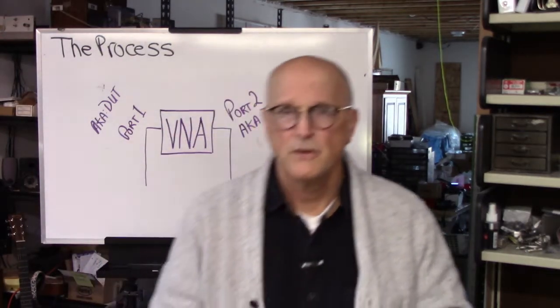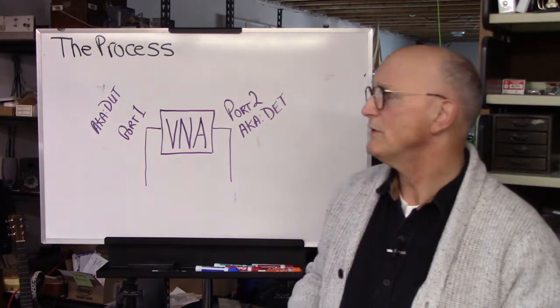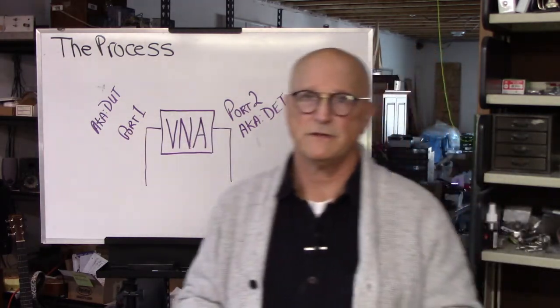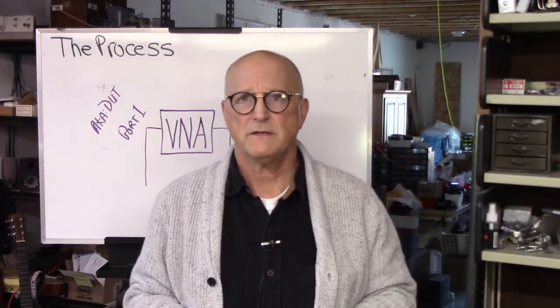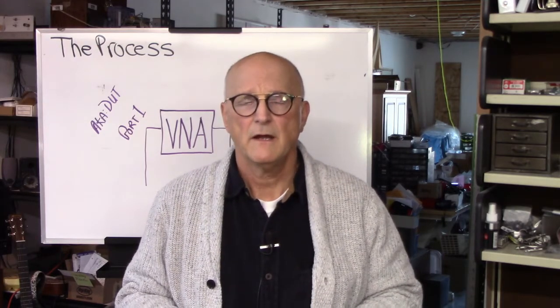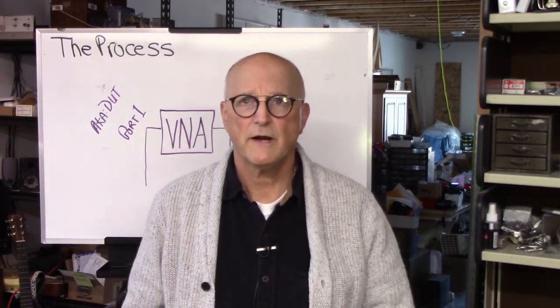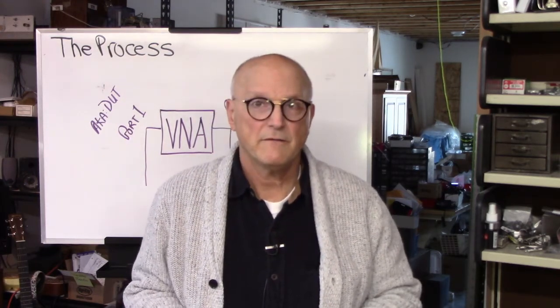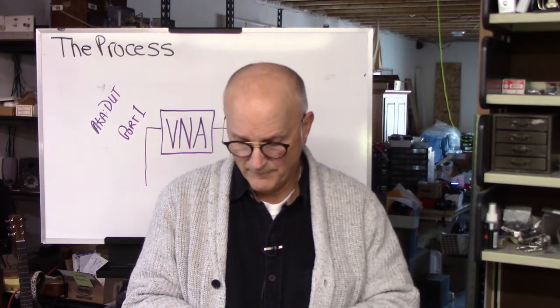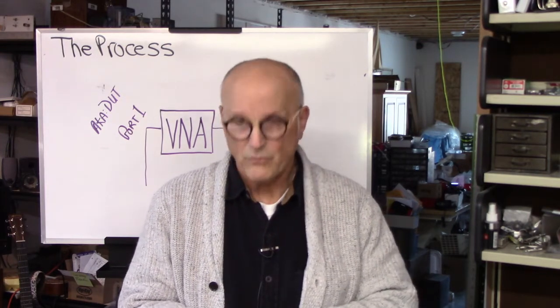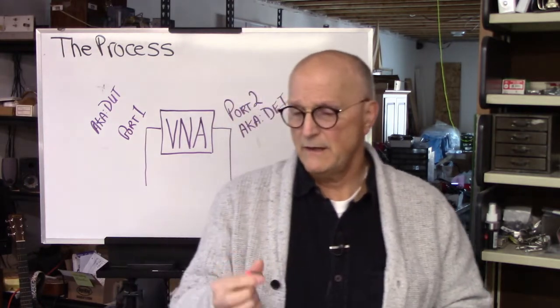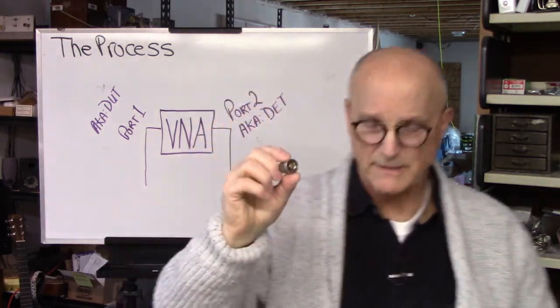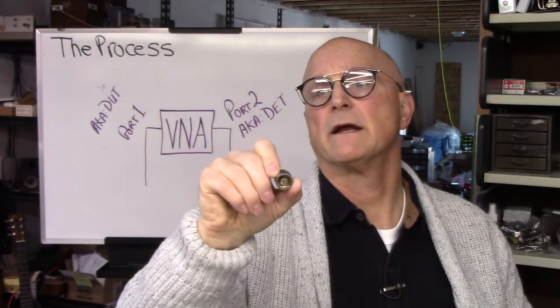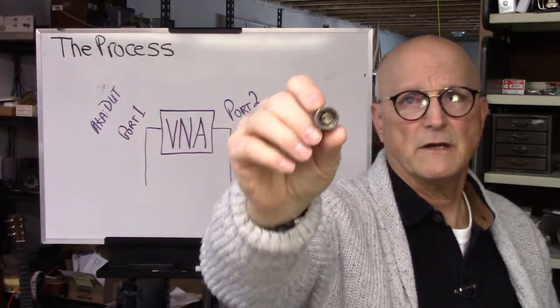Now, you'll need, at the very least, if you do a complete 2-port calibration, and again, what you're going to need of any of these things depends on your particular VNA and the kind of measurements you're trying to accomplish, but I'll talk about that in a little bit. One of the things that you're going to want is an open. And an open needs to be a complete connector. It's not just simply not connecting something to the port or the end of the cable.